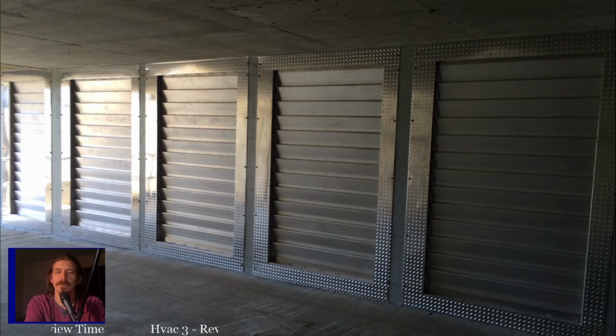What made pneumatic systems very popular and nice in commercial settings for a long time was we didn't have DC controls that could modulate, but you can modulate something with pressure. It's very easy to have a valve that opens all the way at 30 psi or whatever the pressure is, you know what I mean? Opens all the way at 30 psi, is closed all the way at 0 psi, and you can pick a position in between just by changing the pressure going to it. So if you send it 15 psi, it'd be half open. So that's what made pneumatics so popular, is there was a time period there where we didn't have modulating electrical, but we could do modulating with air, and air is extremely good.